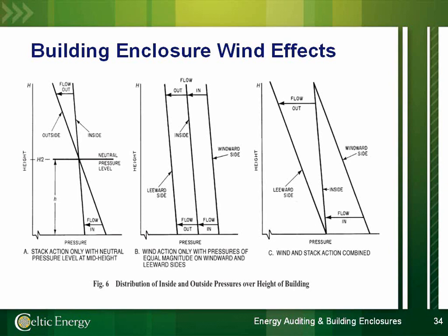The middle graphic shows the effect that you may experience from wind pressure on the side of a building, where it will drive outdoor air into the building through crackage and actually draw it out on the leeward side. And when you combine those two forces, you can see the net effect where you tend to have air entering a building at the bottom and exhausting from a building at the top. And again, this applies to tall buildings. This effect is much less dramatic in a 2 to 5 story building, whereas if you get to a 20-story and higher building, it can become very significant.